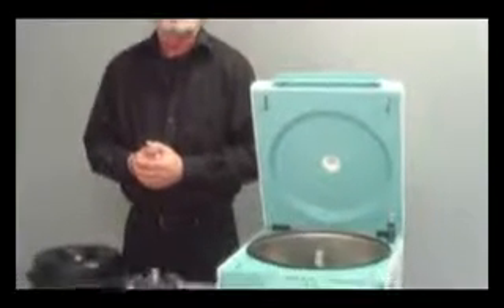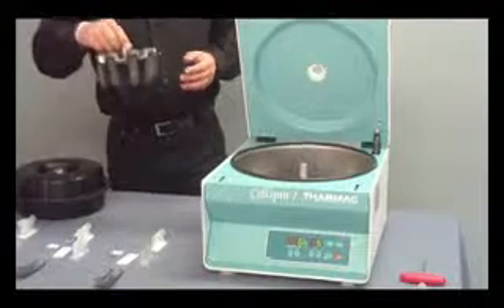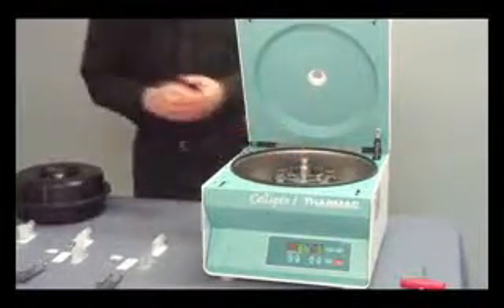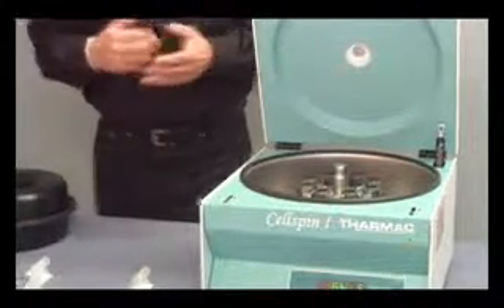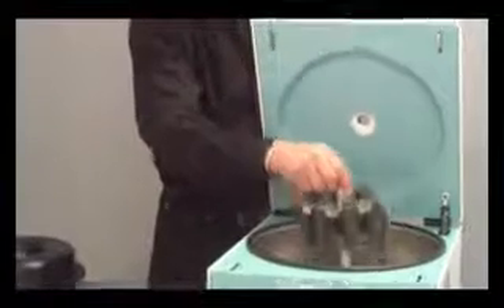The equipment is basically the centrifuge we have here, which is a Cellspin 1 centrifuge, which is a machine you can do 3 tasks with. Task number 1 is a pre-centrifugation with the rotor, so you can do sedimentation on different kind, blood or urines or whatever. At the same time, this machine can be supplied with a cooling unit where you can cool down to about -20 degrees, and for some applications, special in university and research, it is important to keep the specimen cooled when you do the cell preparation. And then, of course, last but not least, you can do the famous cytocentrifugation on this.